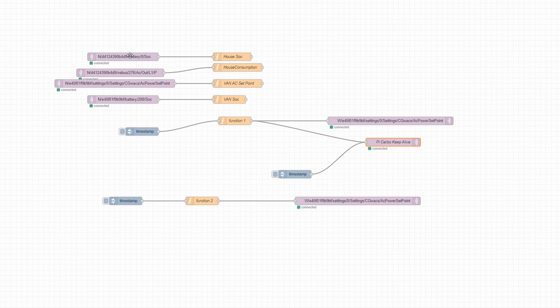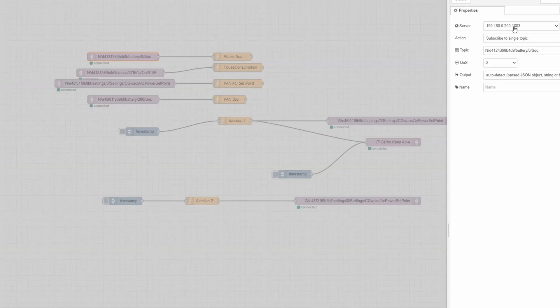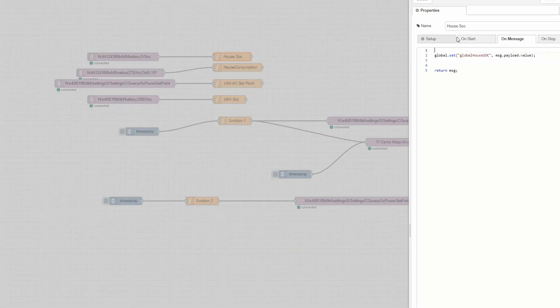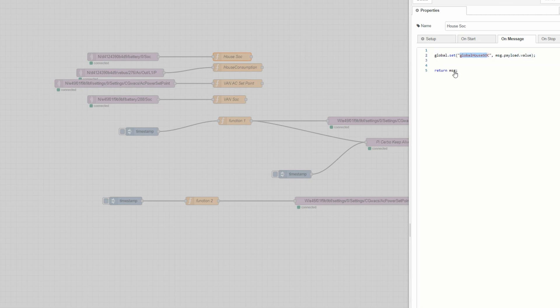That means that if I want to send it negative 50, and I want to send power back to the shed, I can send it negative 50, and it's going to send 50 watts back to the shed. Without pointing out the obvious, that is incredibly dangerous, potentially incredibly dangerous. If you interfere with this in a way that you shouldn't, or you do some unforeseen thing, this could be catastrophic. But we're only going to do this just as a test, just quickly now, I'm not going to leave it like this, and for reasons I'll explain shortly. So to make this happen automatically, we need to, one, know what the house's SOC is.